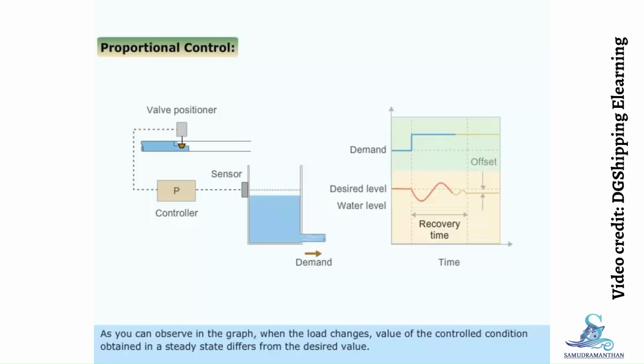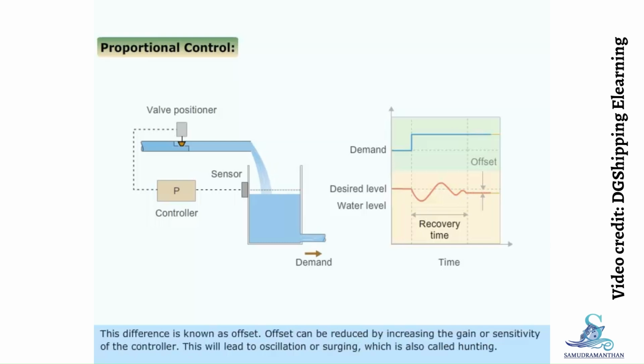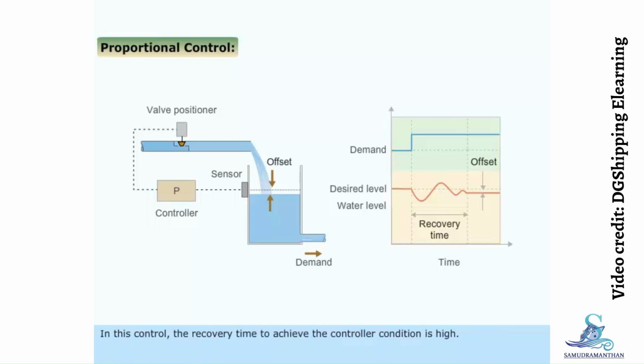As you can observe in the graph, when the load changes, the value of the controlled condition obtained in a steady state differs from the desired value. This difference is known as offset. Offset can be reduced by increasing the gain or sensitivity of the controller. This will lead to oscillation or surging, which is also called hunting. In this control, the recovery time to achieve the controlled condition is high.